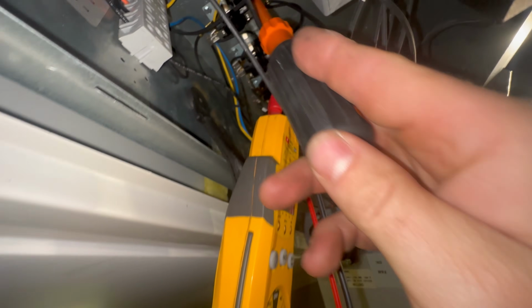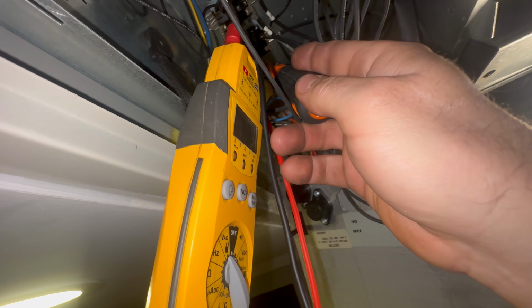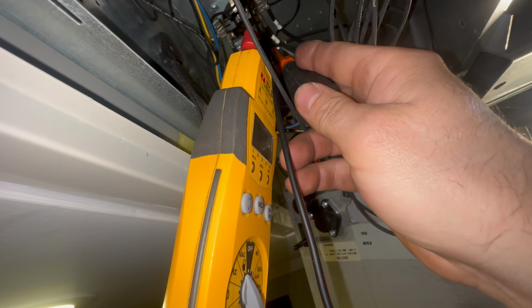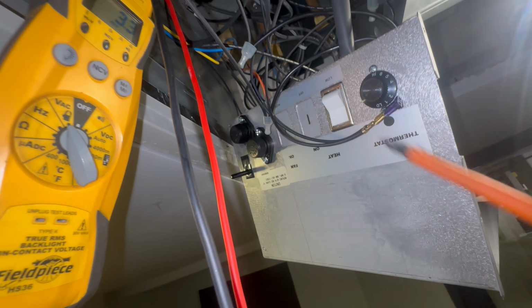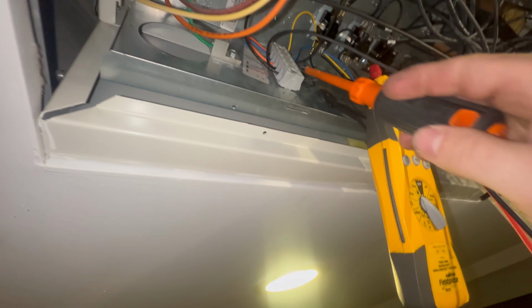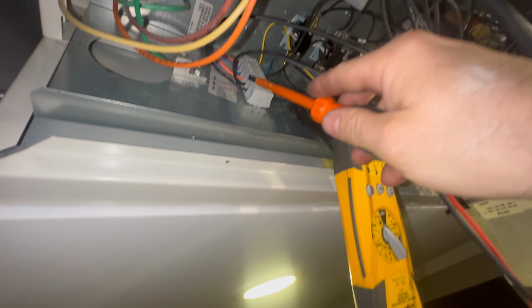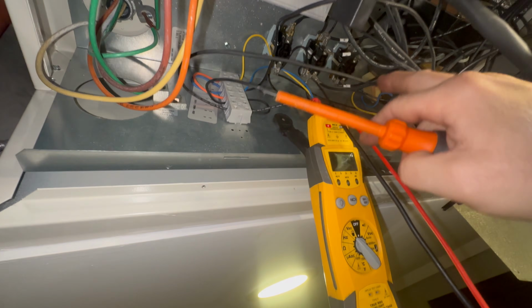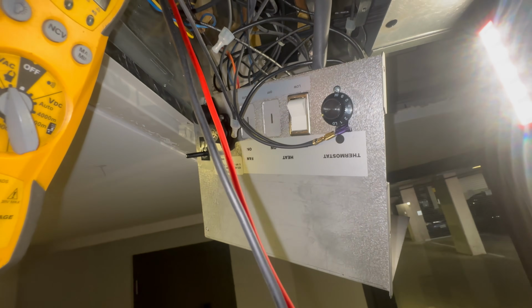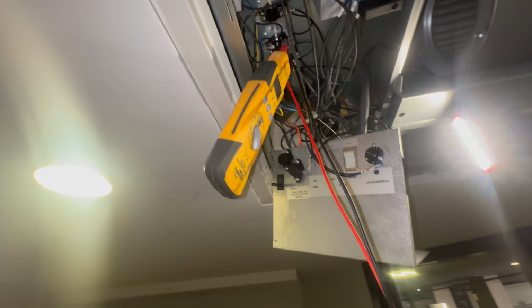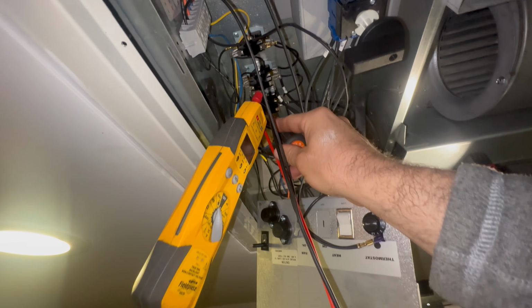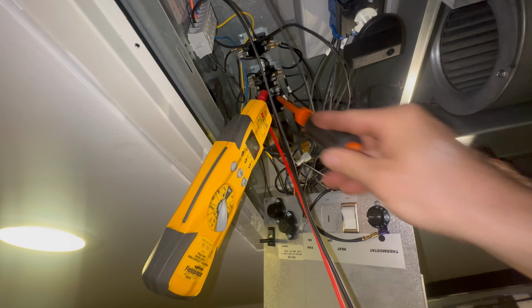On the other side, it is piggybacked, and that 24 volt side goes through our door switch right here. Where this one, if we follow these 2 wires, they go right to here, our thermostat. Pretty easy, and this motor relay, fan motor relay, has a delay on it.